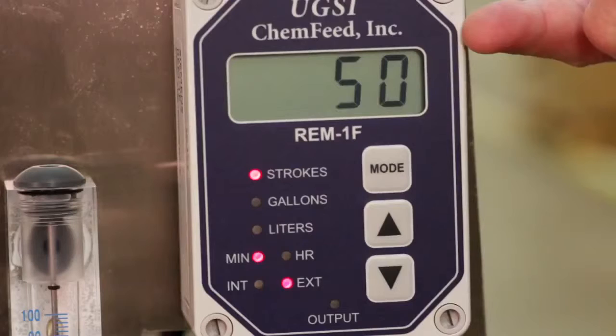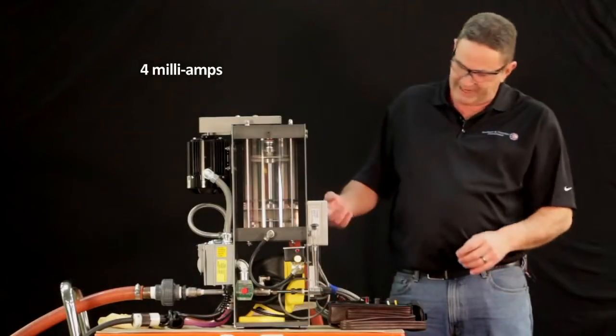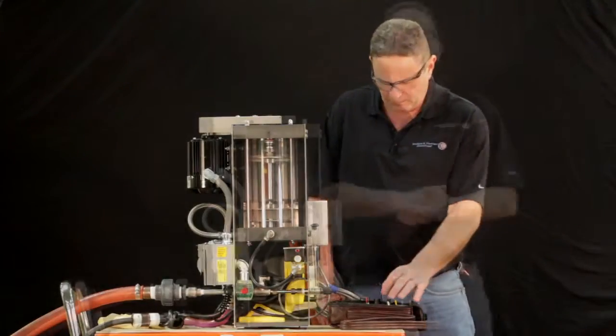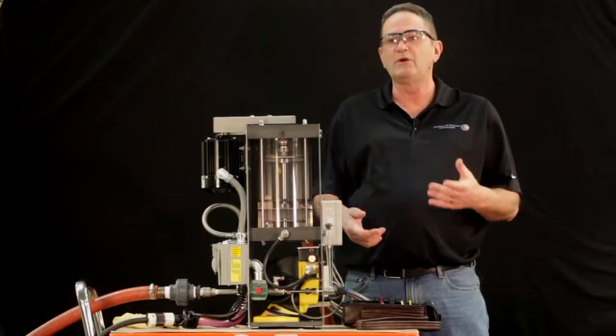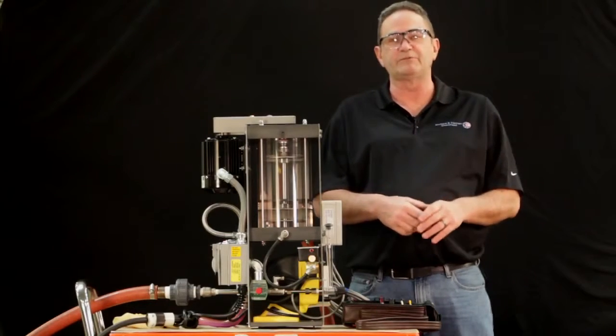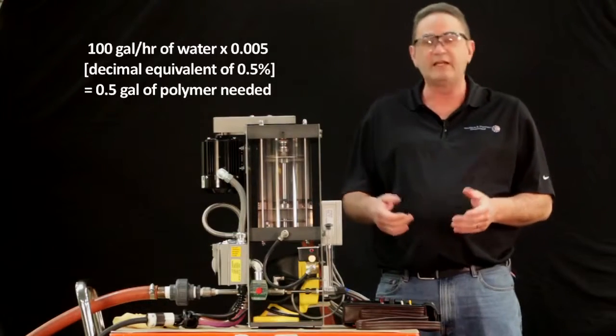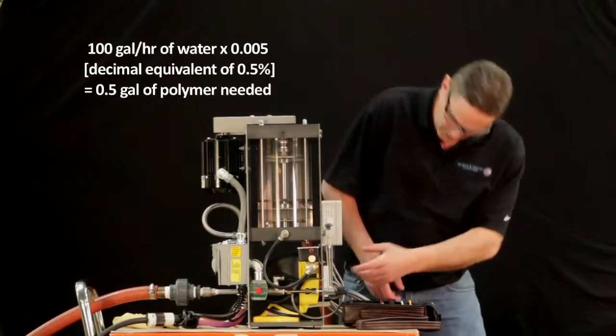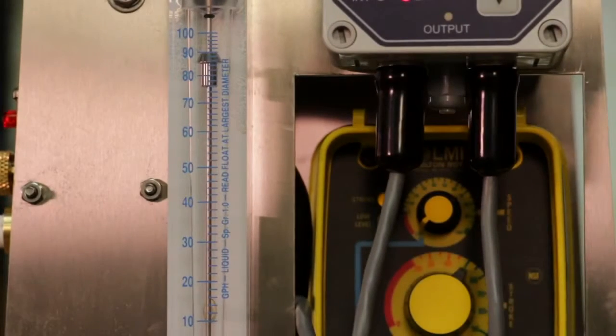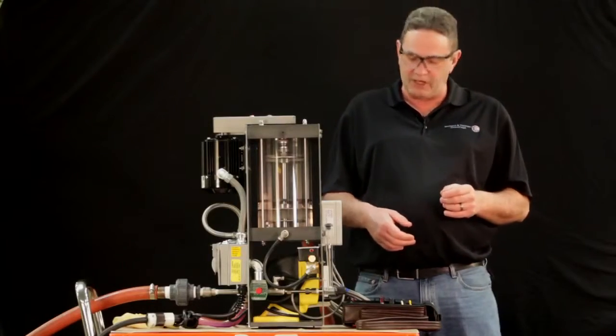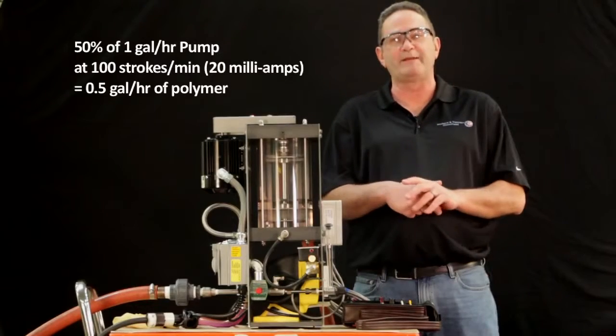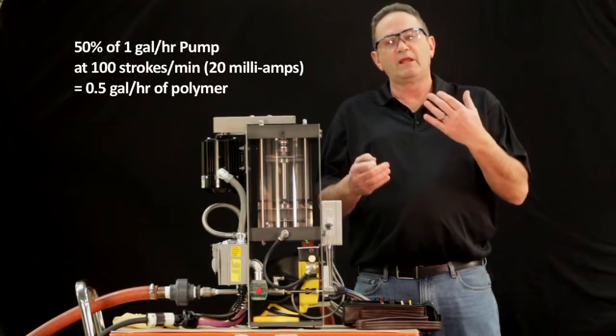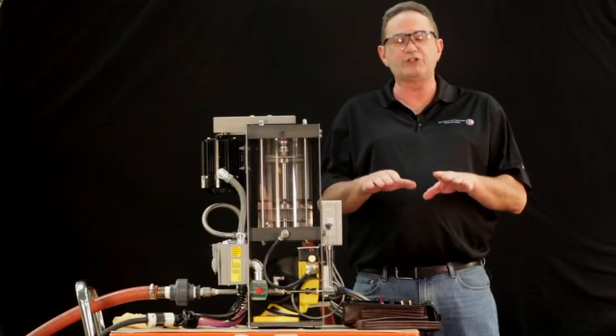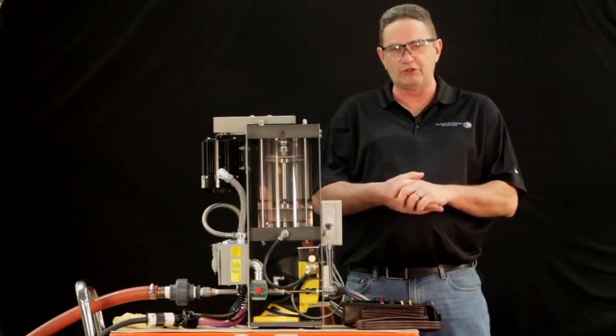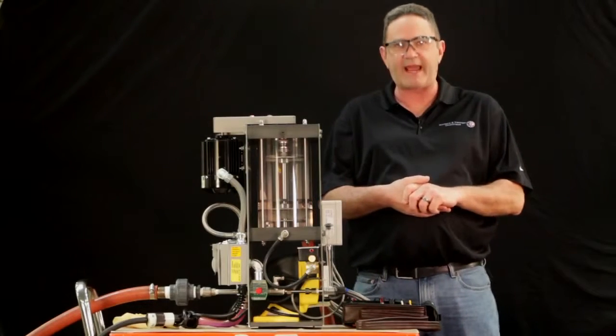12 milliamps, 50 strokes per minute. 4 milliamps, 0 strokes. Now we are in the external mode. We're up in operation. The customer wants 100 gallons at 0.5%. We are at 50% on the polymer pump, 100 strokes per minute.